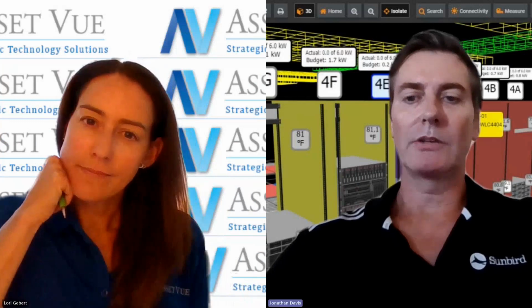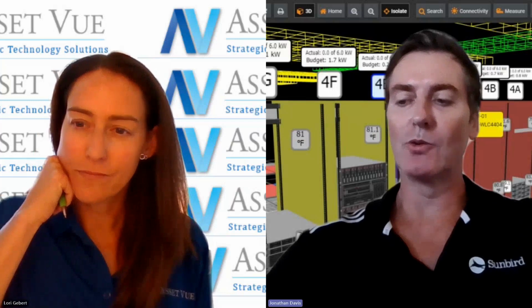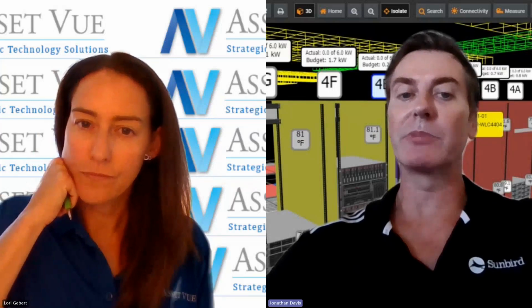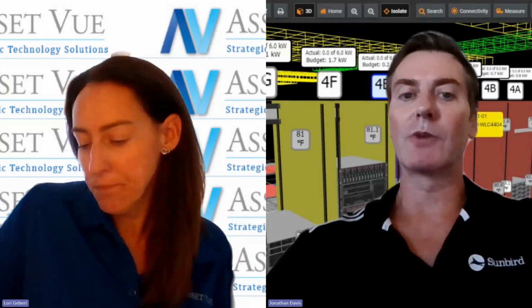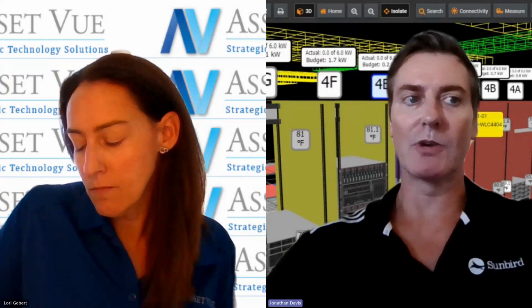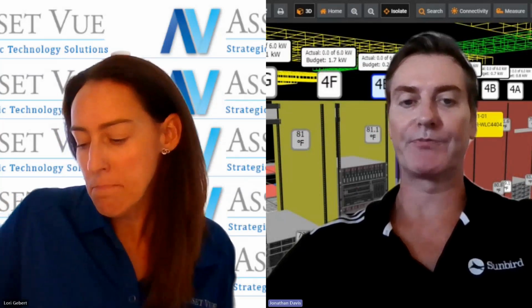What are the challenges? Well, related to what Asset Vue does, having a good baseline of asset data to populate a DCIM and then reconcile periodically, it's a very manual process unless you have a system in place, some automation strategy like barcoding or active or passive RFID. And so what I'm seeing out there is adoption, going from no tool to perform your asset audits to something, either it's barcode, lowest cost, or perhaps a next step up being passive, next step up being active. I don't see a lot of active for asset in the data center.